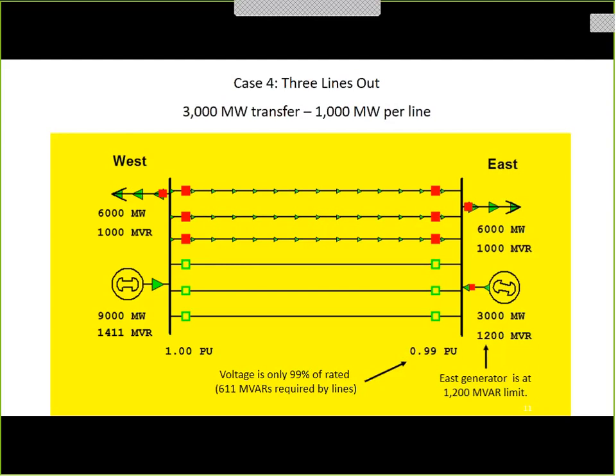The lines are lossy. They have I squared R, which is money. They also have I squared X because they're inductive. Because of that square, it goes up, because the current is going over there. For example, now the current, I don't know, is 1,000 mega amps per line. You square that, you're going to get more than before. So this is still at its VAR limit. It can't produce any more than 1,200. That's all it's got. The voltage is starting to go down because of that.